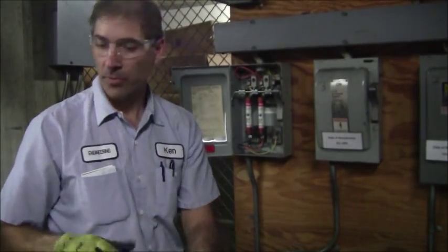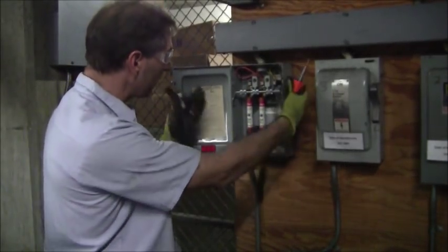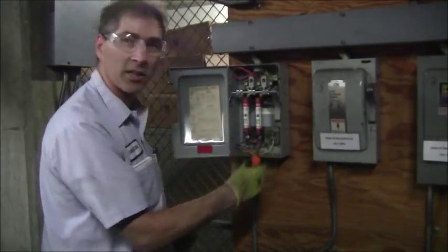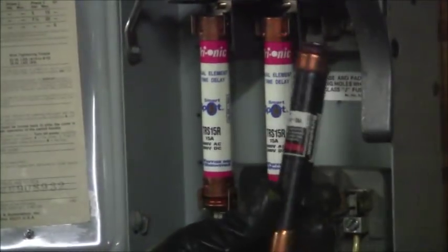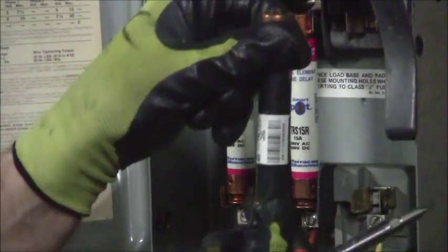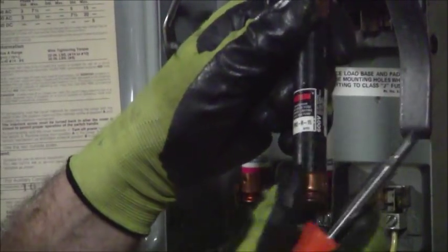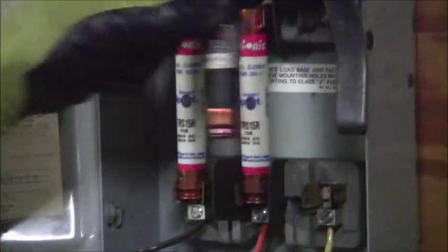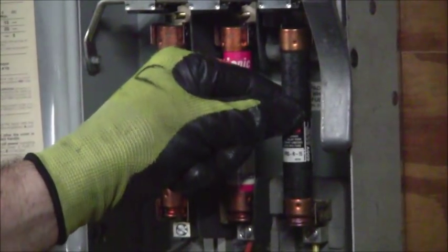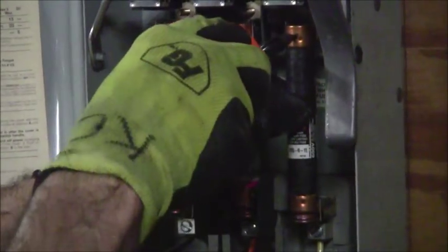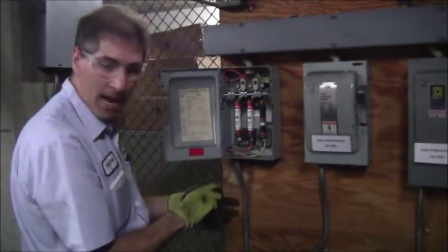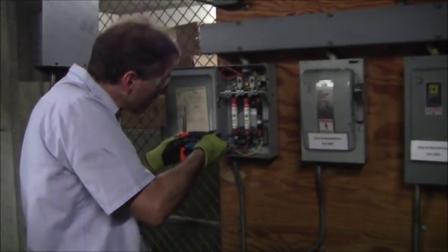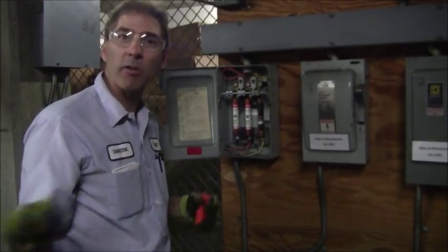So now I'm going to put my fuse in here. Everything is still off. I'm live at the top, dead at the bottom. When you put your fuse in, don't put it in upside down. Don't put it in so that the numbers are in the back, and don't disturb the writing that tells you what the fuse is. I'm just going to put it right side up, facing towards me, put it in like so, and I like to push them in with just a flat-bladed screwdriver. And it just snaps right in, okay? If it did not snap in, I would take my channel locks, pinch that down slightly just to give it a really good tight fit.